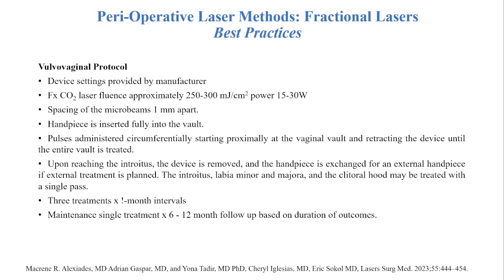We administer the pulse circumferentially. It really only takes 5 minutes to treat, and we retract about 1 centimeter per round of firing the handpiece, so that the typical vaginal length is about 8 to 10 centimeters. So it is a very quick treatment, and it's 3 treatments at 1-month intervals, and maintenance treatments are done at 6 to 12 months.